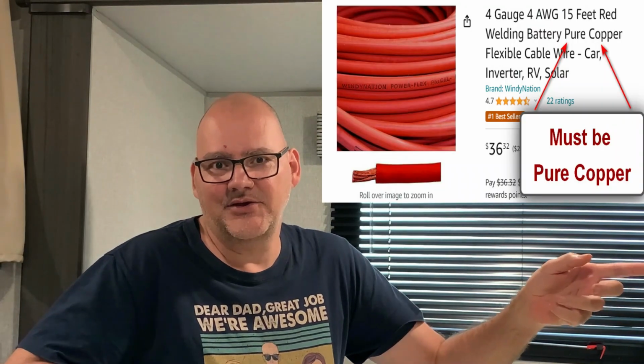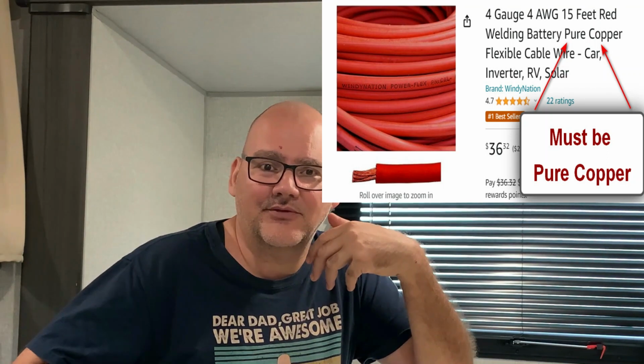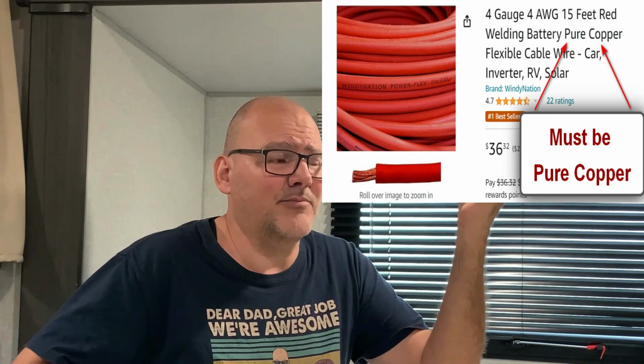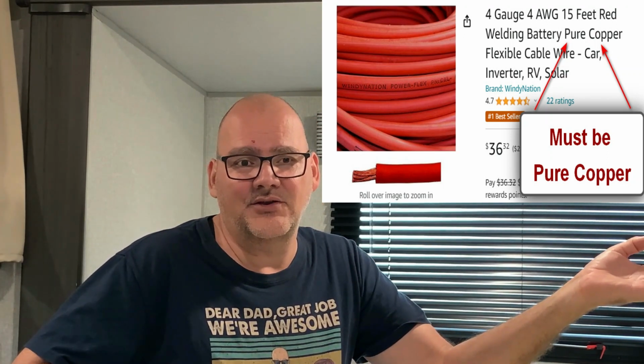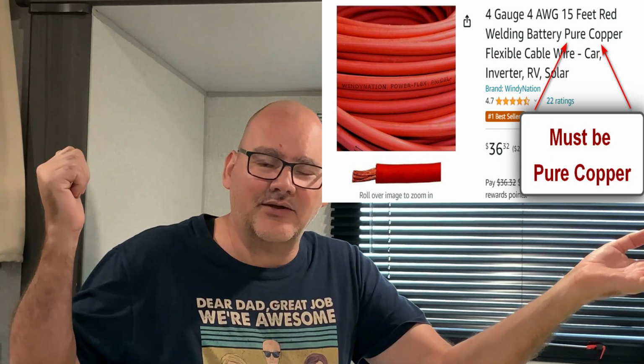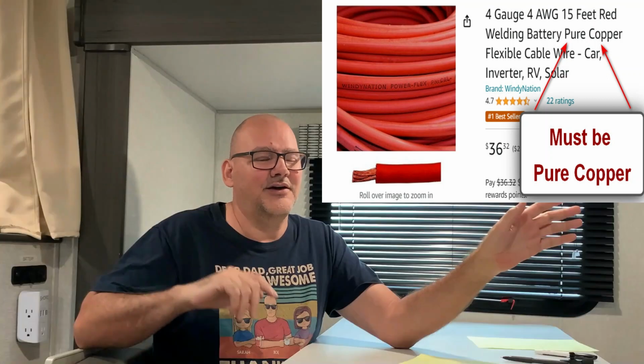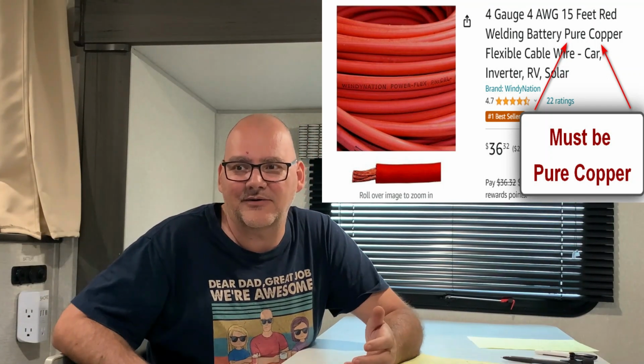Another problem people cause is having too small of a cable coming from their battery to the inverter or whatever they're running off the battery pack. Let's say your battery is way up front on the tongue and your inverter is way at the back of the RV. You shouldn't do that to begin with, but let's say it is. That length of the RV could be 15, 20 feet, and because of the cable length on a 12 volt system, you're going to need a massive cable to get that power all the way to that spot. So if you're running an inverter, try to put it as close to your battery source as possible, so you don't have to run a massive cable to it.